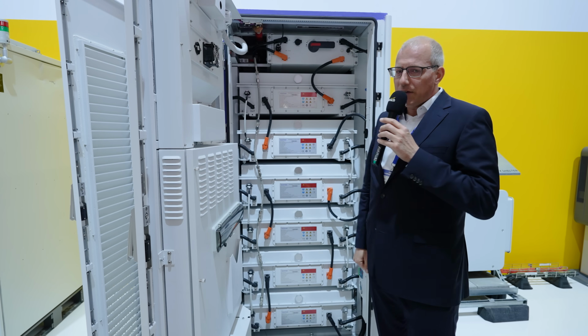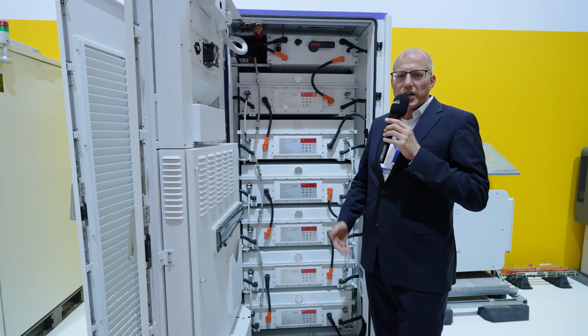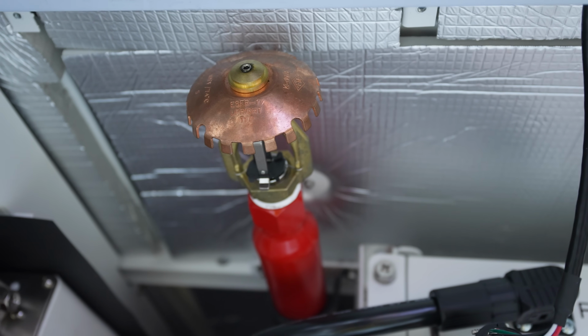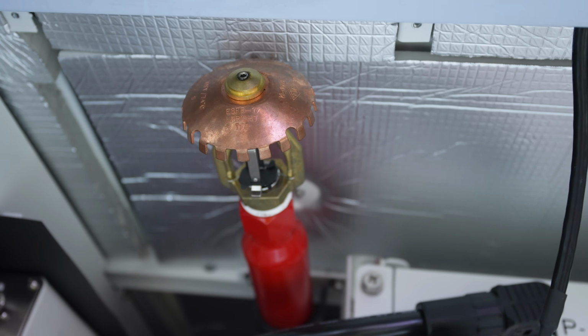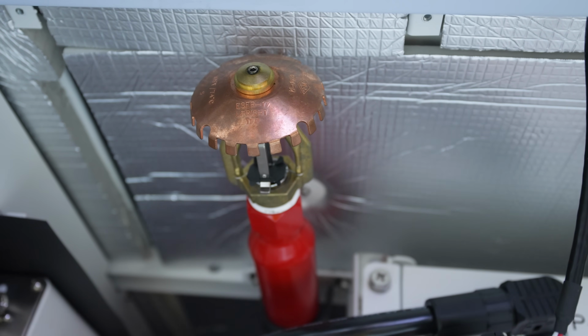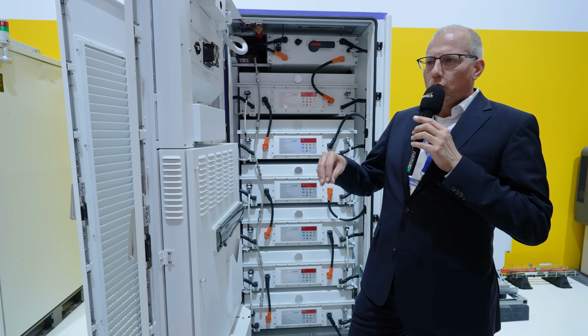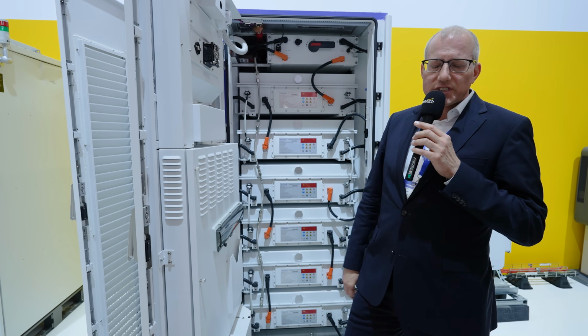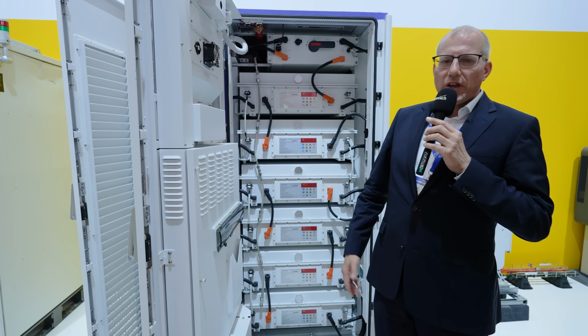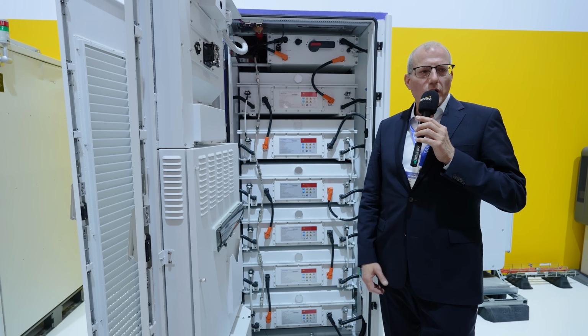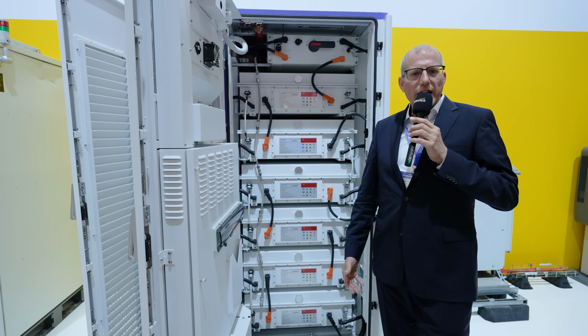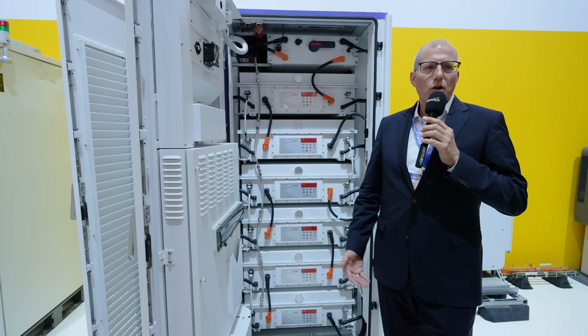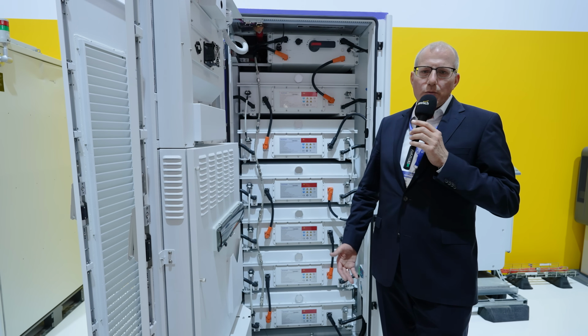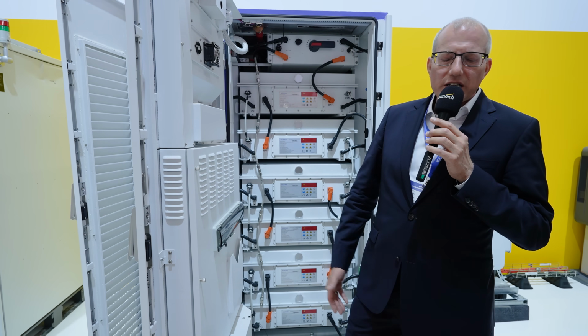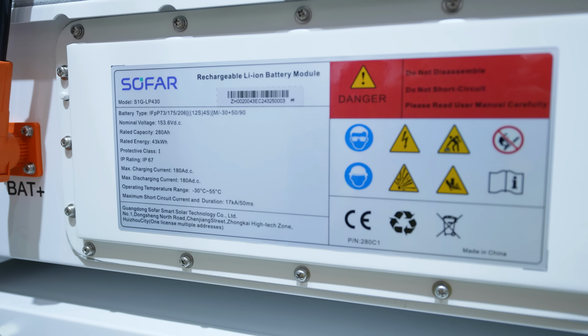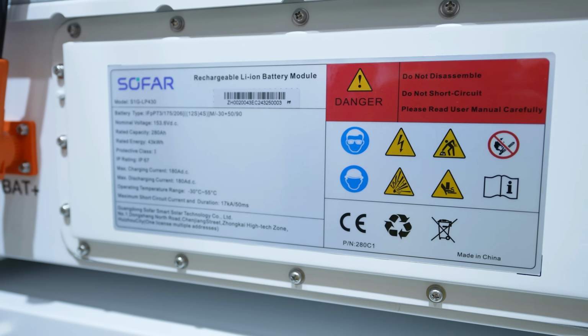We also have safety systems for fire protection, the sprinkler system. We also have the protection gas, perfluorohexanone gas, which, in the case of any temperature increase, will be emitted to keep the cells cool and safe. There's also a fireman's connection for the hose of the fire brigade, in case you want to flood the whole container when it's overheating. Anyway, our cells are LFP technology, which is the safest technology on the market, so you don't need to worry about this case.